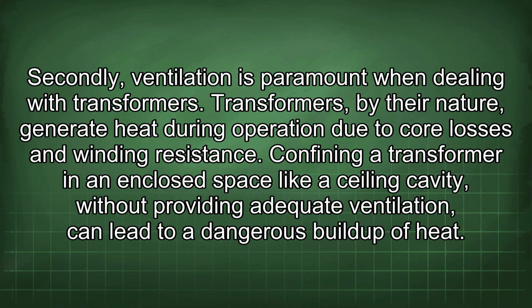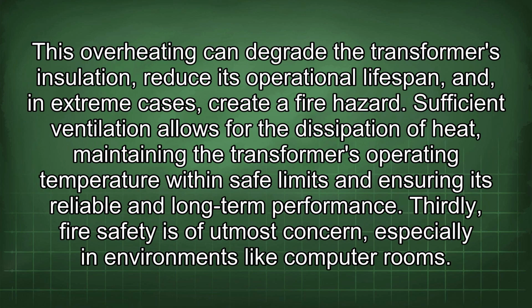Secondly, ventilation is paramount when dealing with transformers. Transformers, by their nature, generate heat during operation due to core losses and winding resistance. Confining a transformer in an enclosed space like a ceiling cavity, without providing adequate ventilation, can lead to a dangerous buildup of heat. This overheating can degrade the transformer's insulation, reduce its operational lifespan, and, in extreme cases, create a fire hazard. Sufficient ventilation allows for the dissipation of heat, maintaining the transformer's operating temperature within safe limits and ensuring its reliable and long-term performance.